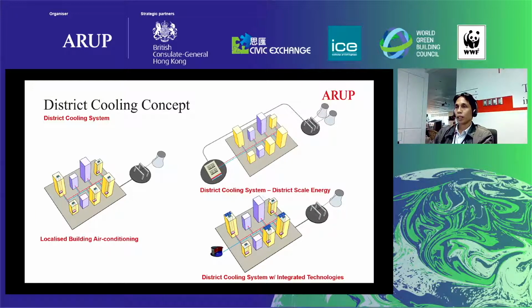In terms of the concept for a district cooling system, typically an air-conditioned building has a localized air conditioning plant, similar to the image at the left portion of this slide. For a conventional type DCS, we have a central energy plant that houses all the chillers, pumps, cooling towers, and an electrical substation connected to the grid.